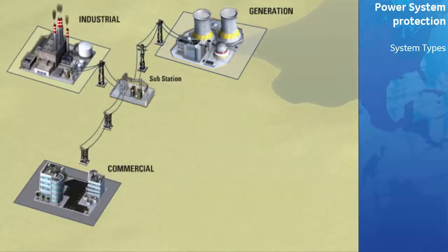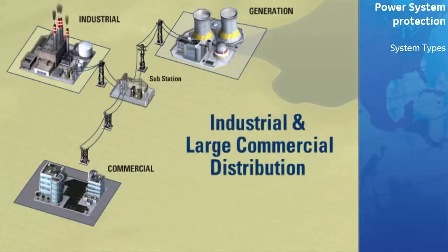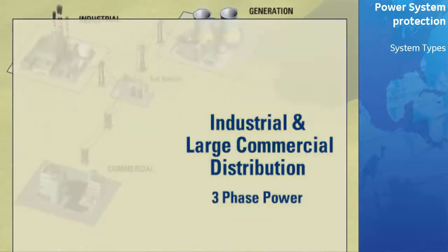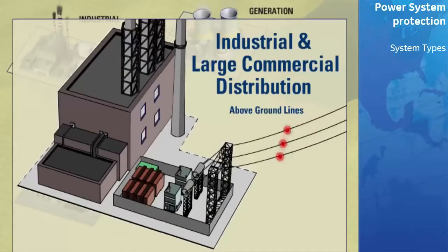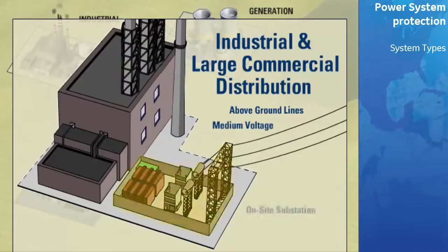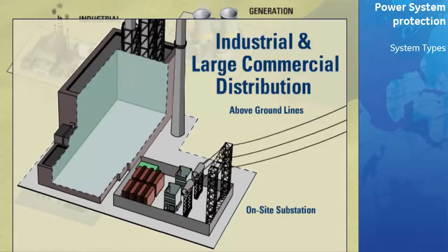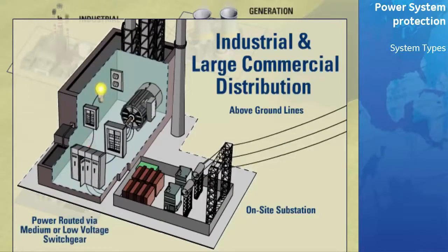The distribution system for a typical industrial or commercial user shares some similarities to that of the residential customer, with the major exception that the power being delivered is usually three-phase. From the substation, the industrial or commercial power lines take the power above or below ground to a large transformer, which steps the three-phase voltage down to a suitable level for the plant or building. For larger commercial or industrial users, this voltage may be in the medium voltage range, in which case there will be an additional substation on site. The power would then be routed from the transformer or transformers via medium or low voltage switchgear to different areas of the plant or building for further distribution via switchboards and panel boards.